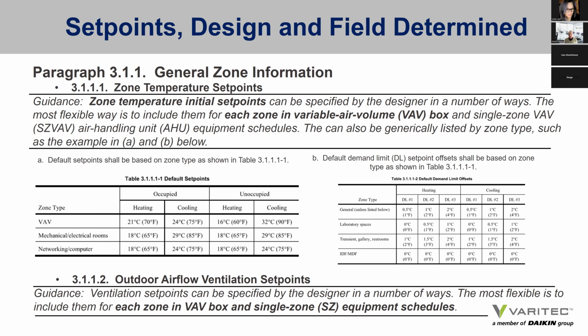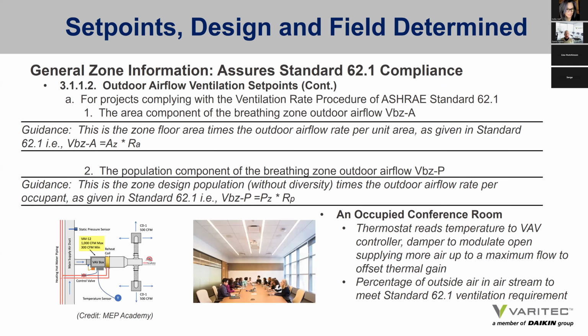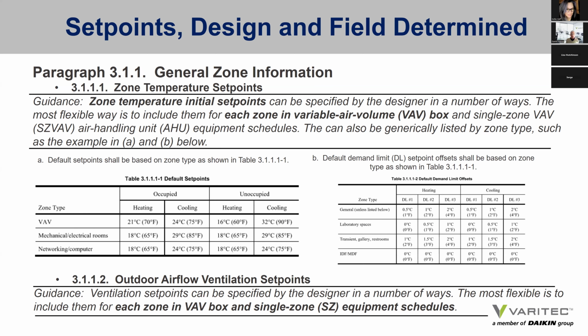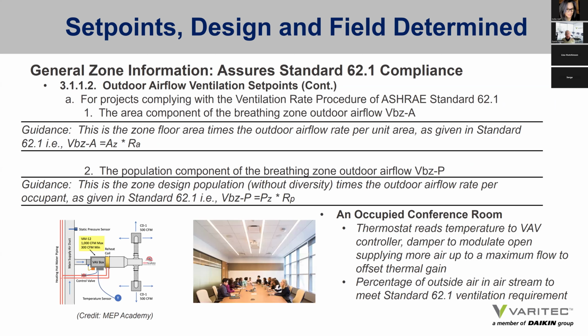And the most flexible is to include them in each zone VAV box so that it can actually be measured how much outside air is being served and delivered to each zone, to make sure that an indoor air quality level is being maintained. There are outdoor airflow ventilation set points, and the guideline leans on ASHRAE Standard 62.1 as the standard to define how much outside air needs to be provided to each zone.